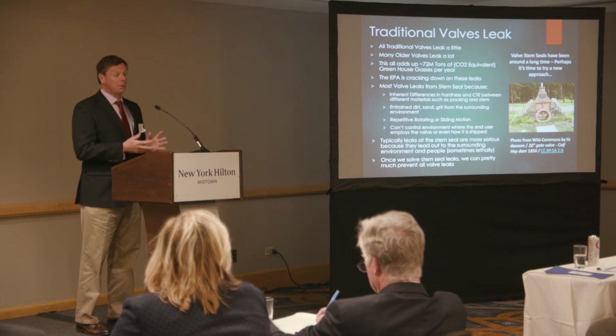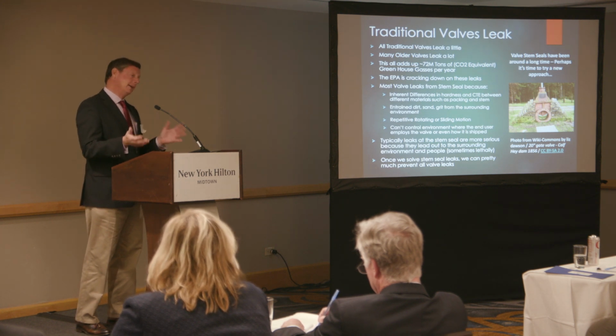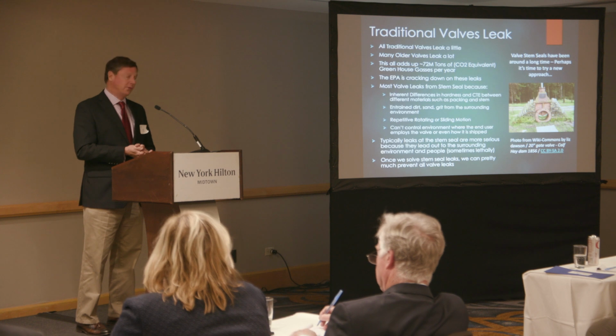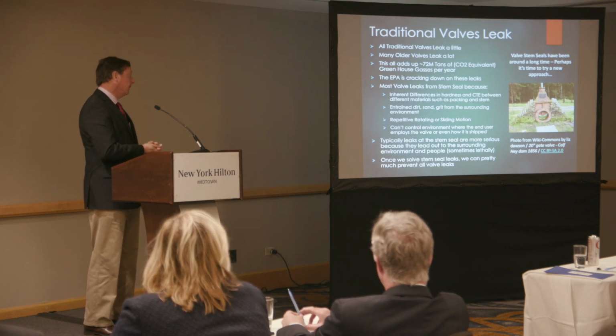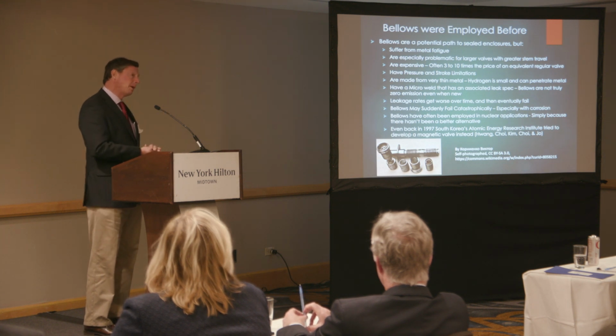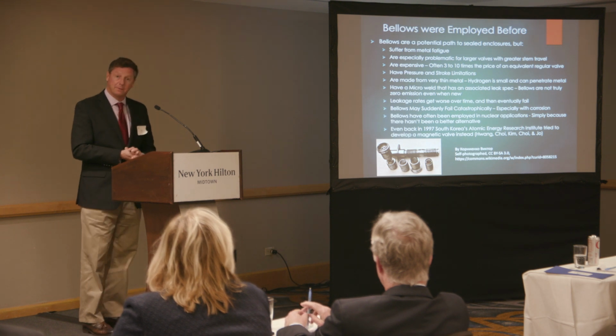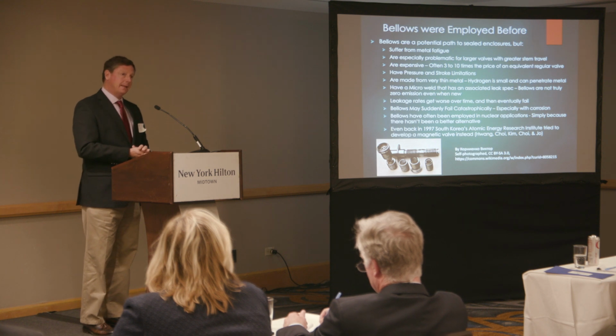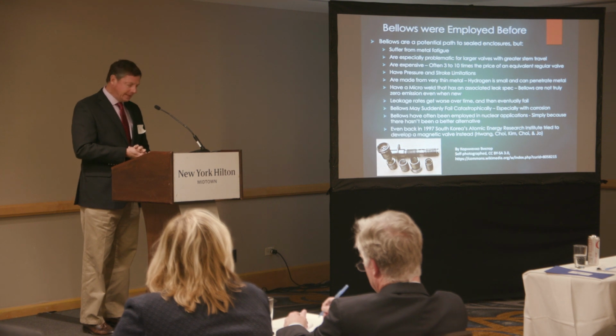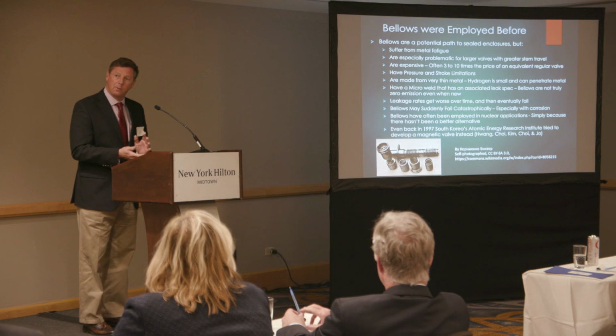In certain refining processes like HF alky, leaks can be fatal, and certainly in other industries like semiconductors. Caitlin, if we can go to the next slide. This is probably the nearest competing technology to ours, bellows valves, used extensively, for example, in the nuclear industry. It's not perfect. The valve subject matter expert I know from Shell said, Ned, it isn't really if the bellows valve is going to leak. It's more a question of when.